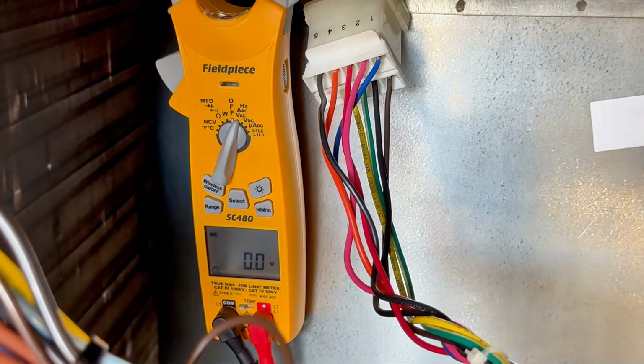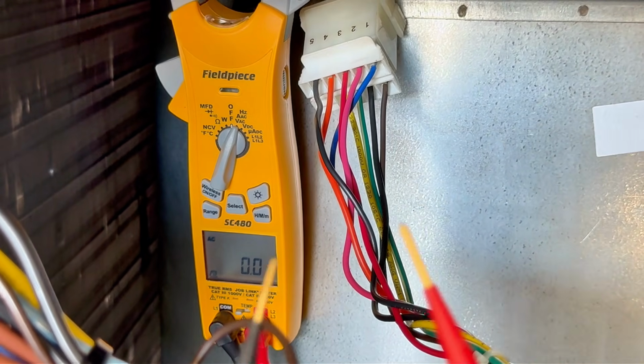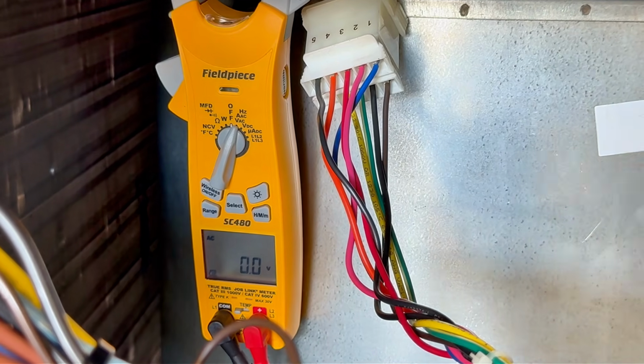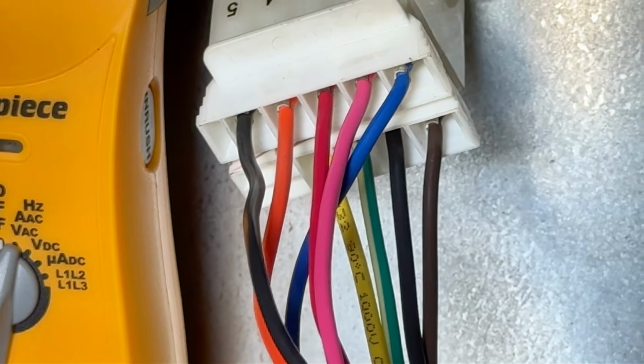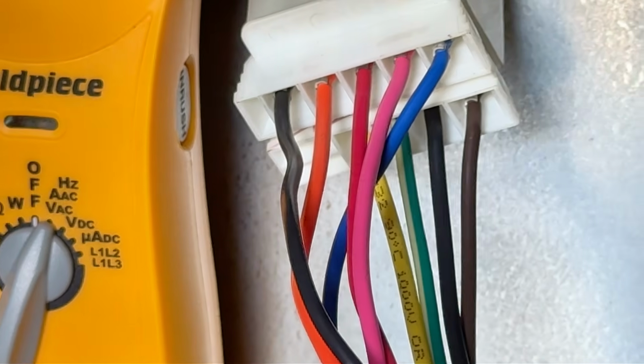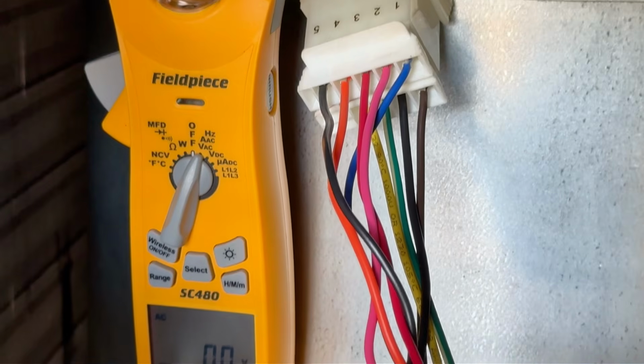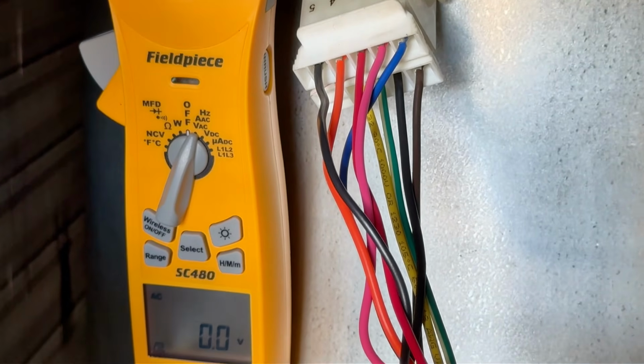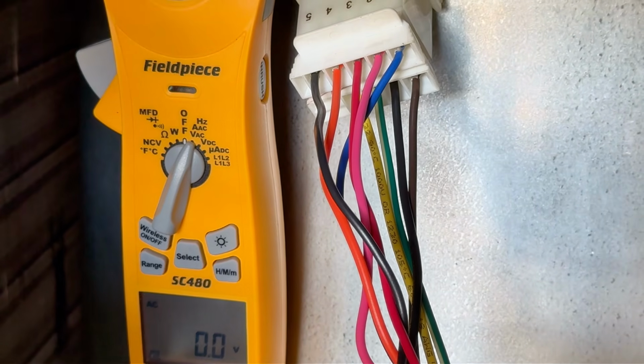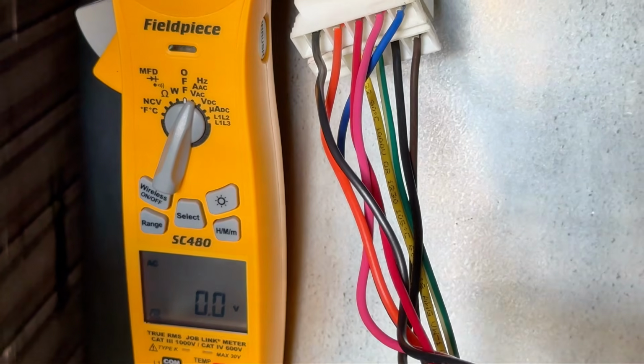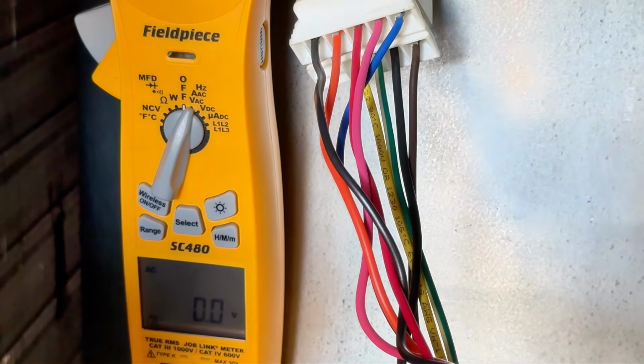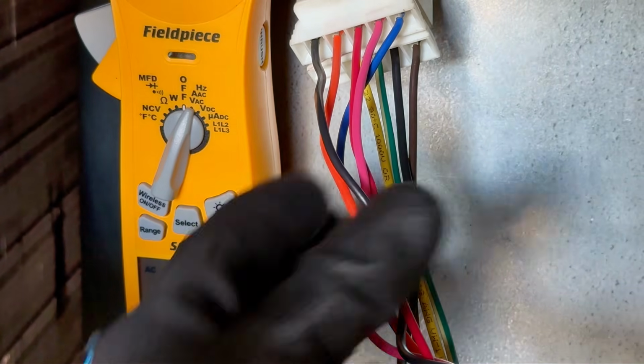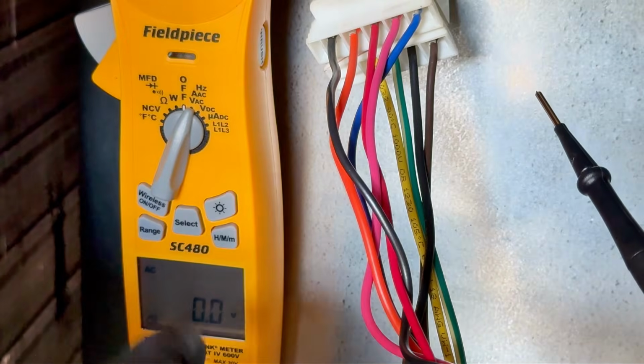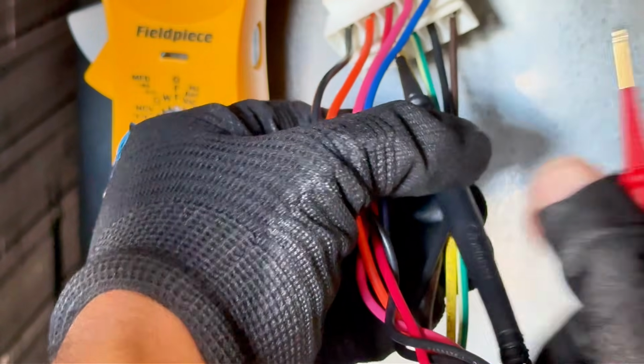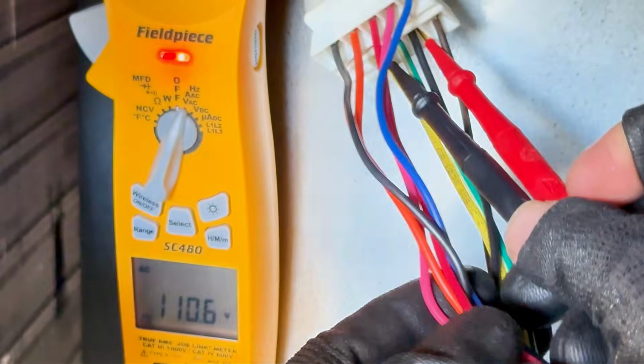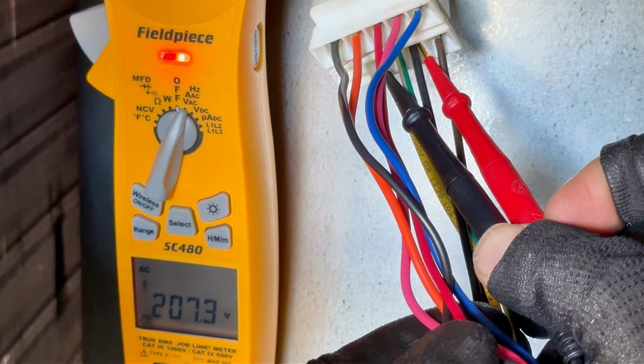Okay, so what we're gonna do, you can do it with these leads here. Typically, you do want to use a skinnier lead, but if you notice on this specific plug, I do have enough space to put it on the back without damaging the wires and the connections there. So let's go ahead and check first for high voltage, okay? All I'm doing is checking my black and my yellow because that's my high voltage. I'll move my hand right now so you can see the voltage here. I'm gonna put it on the yellow one, and on the black, just push it all the way in. You see that? I'm getting 208, okay?